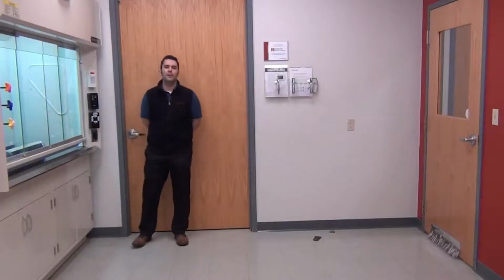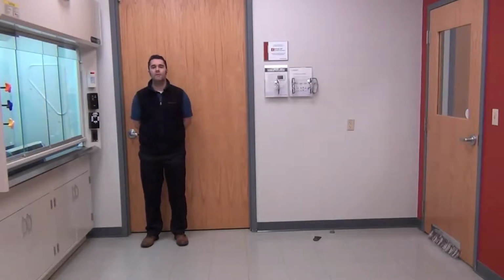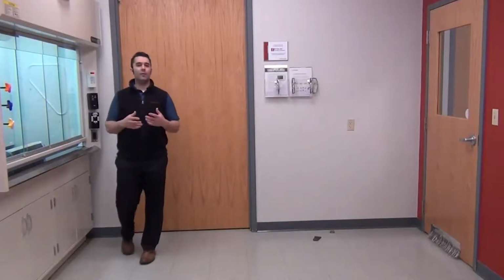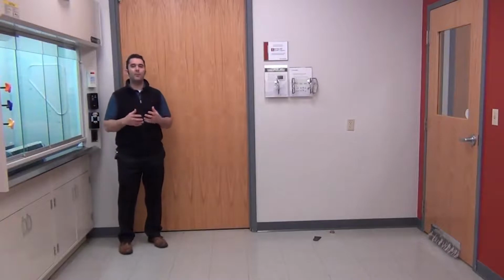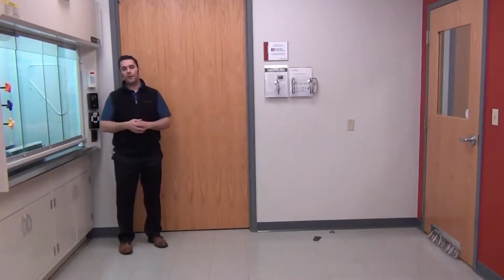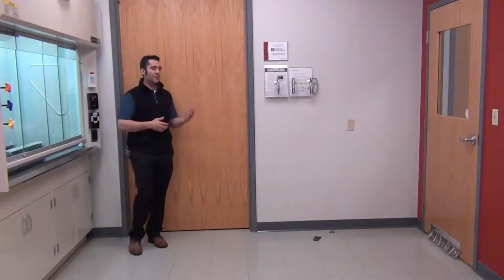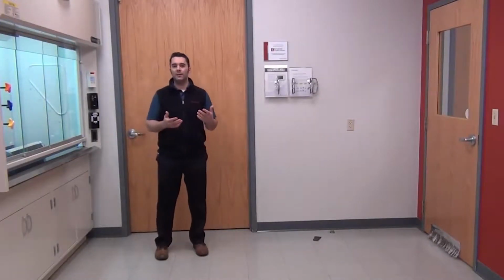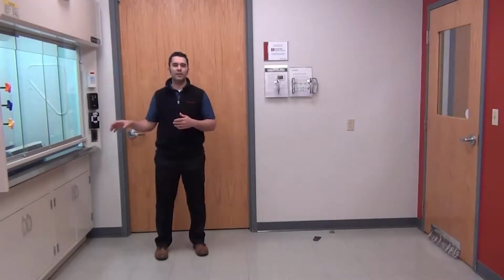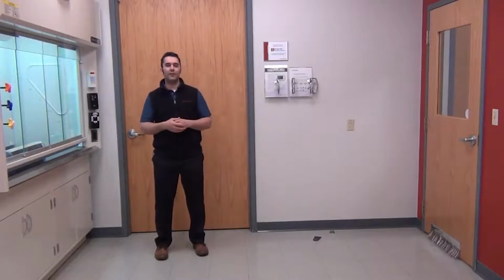So now that we've talked a little bit about the fume hoods and the technology that we at Phoenix Controls have, I also want to talk a little bit about the entire envelope inside of a wet chemistry lab. And what I mean by an envelope is the pressure relationship between this space and the adjacent spaces. So the reason that this is important, a lot of times we hear about value engineering a job. It's very important to keep the cost low to the customer while providing them the best equipment that you can. Now the trap that a lot of people fall into in a wet chemistry lab is they say, well, you've proven to me that I need a 1-second speed of response on my fume hood, but I really think that I can get away with a VAV box or some other flow measurement device for my general exhaust and my supply air inside of this lab.